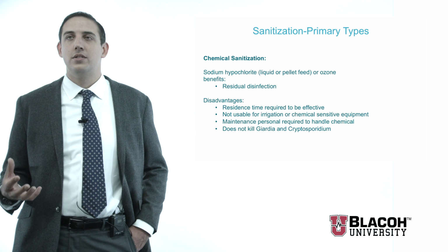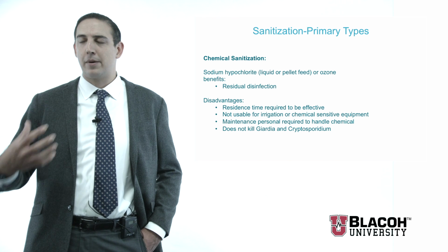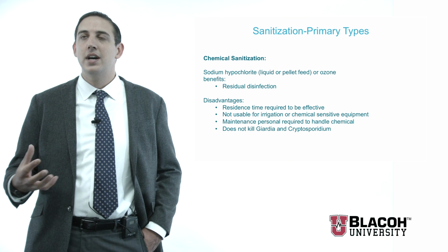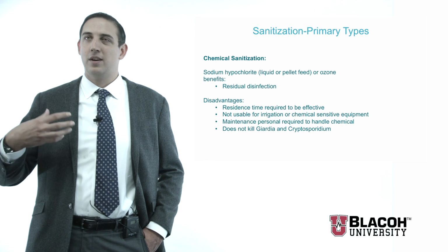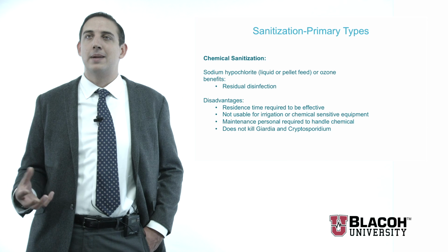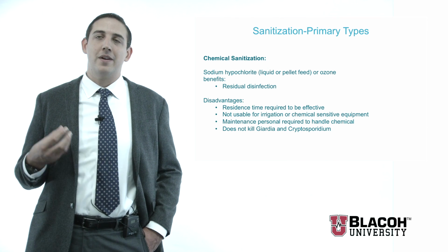Chlorine is used in some applications. The downside to chlorine is, one, I now have a chemical that I'm introducing into my system. I also now have to have somebody actually watch this. Now, of course, I'm taking what is relatively considered a green process, and I'm introducing this now chemical to it. It also requires a fair amount of contact time.